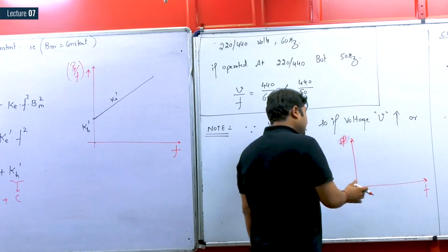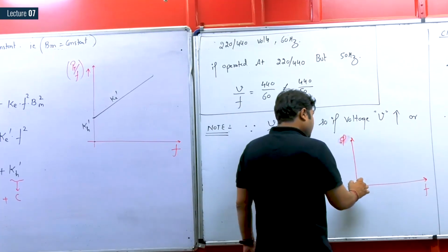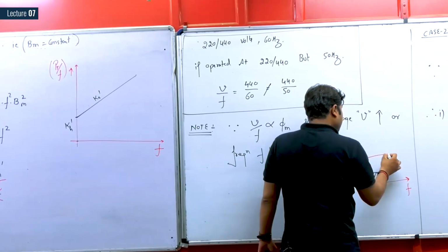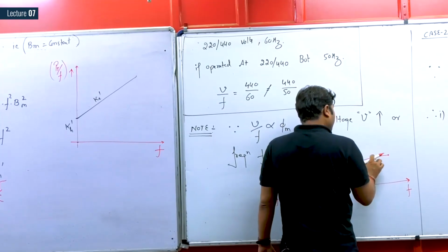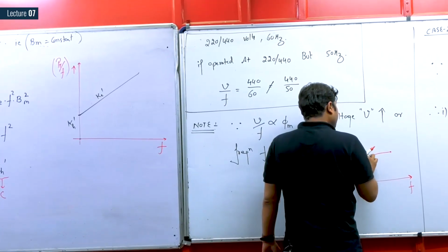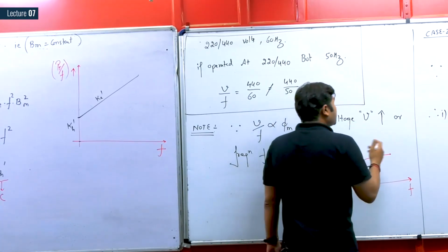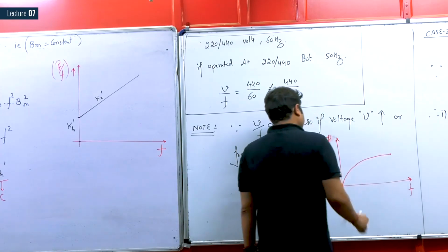If the decrement in frequency is very high, then the transformer goes into deep saturation, and definitely the losses increase. Also, if the material is a hard magnetic material and the frequency is reduced by a very large amount, the transformer core may get permanently magnetized in one direction.